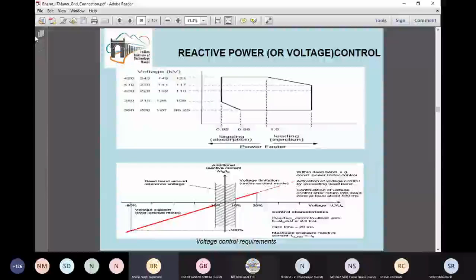So this slide shows how many operating zones there are when we are talking about voltage control. Please see the figure below, which shows how much reactive power is required. Both of these curves are from the German grid code, and similar curves are also there in the Indian grid code. In the figure below, the y-axis is the additional reactive current requirement, and the x-axis is the voltage.